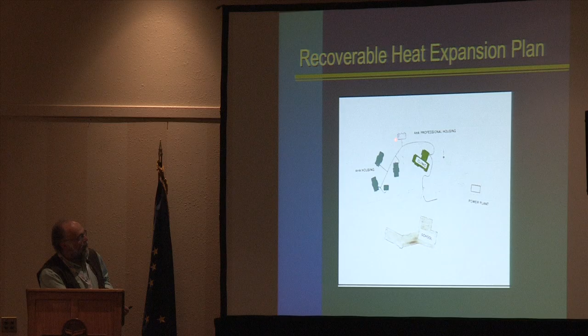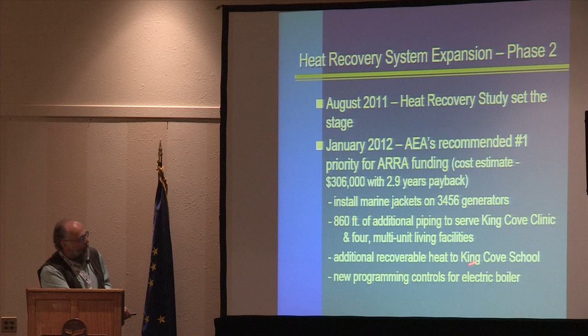2012, AEA's recommended number one priority. Back in those days, ARRA funding — everybody remembers what that was all about — we happened to be in the right place at the right time. The cost estimate to do the expansion was $306,000 with a 2.9-year payback. In the end, the project actually cost about $350,000, because we added the other units I talked about. It involved installing marine jackets on the 3, 4, 5, 6 units, which Mark talked about, and 860 feet of additional piping, which ended up being a bit more than that to extend to the other units, plus additional recoverable heat to the King Cove School.